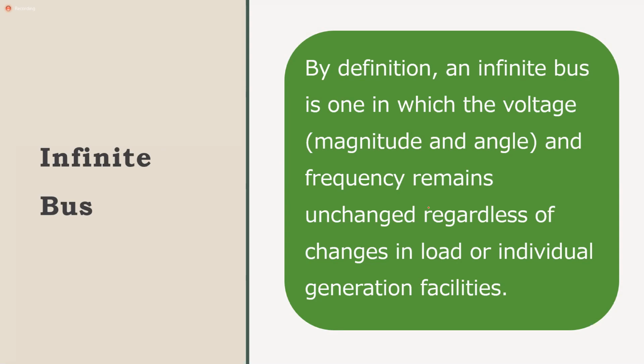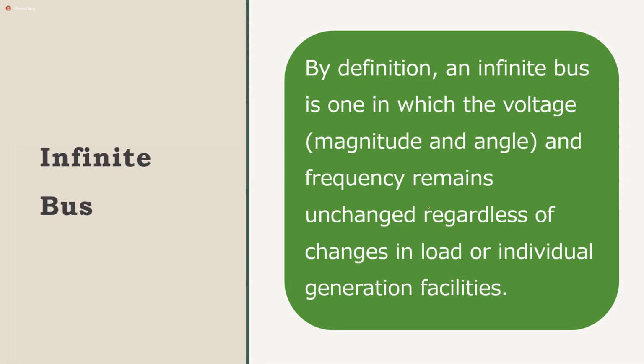Do we understand that? Is that clear? Yes sir. All right, so if I'm connecting a unit to the bus, that unit must conform to the conditions. Even if the unit isn't fully in sync with the network, because it's being added to an infinite bus, the bus will pull it into synchronism. Meaning when it joins the infinite bus, the frequency of that incoming unit will now conform to the frequency of the infinite bus, because of the existence of all these generators.